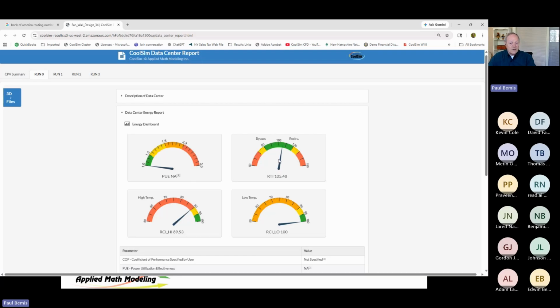This could be for a variety of reasons. It could be altitude that's causing this. Could be this is up in the air. And even though I set my initial boundary conditions correctly to have enough air, I don't have the density. And so I'm having trouble cooling it at high altitude. It could also be that we have high temperatures running in this data center. Temperature will affect flow rate, again, because of density.